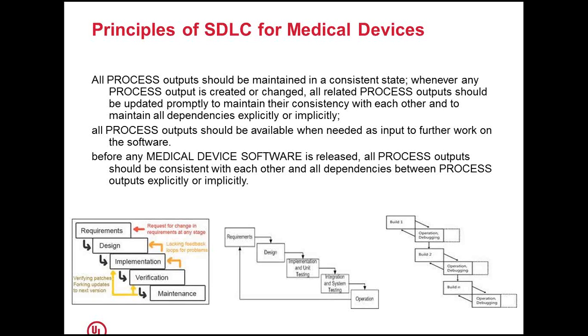Irrespective of the model used for development, there are certain principles to be followed for medical devices. The standard clearly specifies that all outputs should be maintained in a consistent state — whenever any process output is created or changed, all related outputs should be updated promptly to maintain consistency and to maintain all dependencies explicitly or implicitly. Whatever changes are made throughout the process at any stage, you need to review them completely, assess the overall impact, and take actions to update wherever needed — even if it requires going back to redefine requirements from a testing phase.